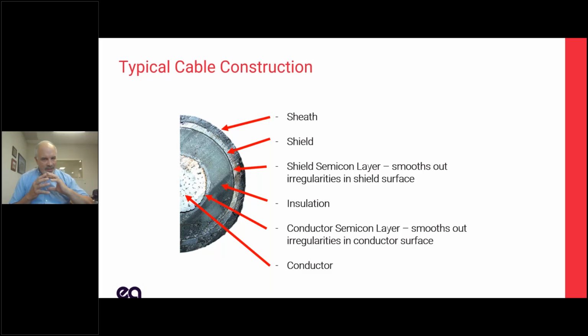So what we have is, in a cable, we have a conductor. That conductor is not smooth on the outside. Imagine a stranded conductor. It's got bumps from the individual conductors. And so we put a semicon layer on that that smooths it out. Then we have our insulator. Then we have another semicon layer that's there just inside the shield to smooth out any irregularities in the shield, especially when you have a concentric neutral where you have wires that are spaced apart. We want to provide a perfectly even conductive layer on the outside.